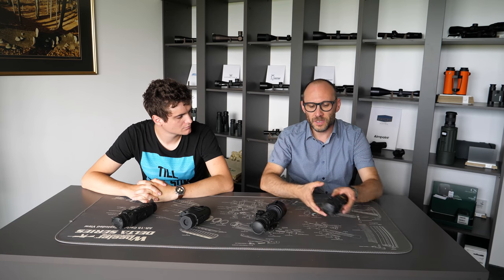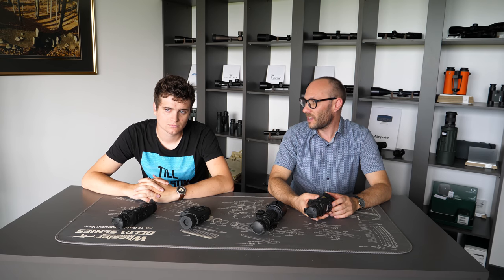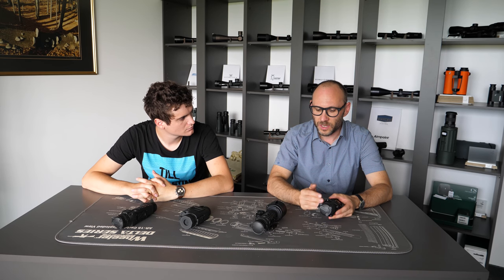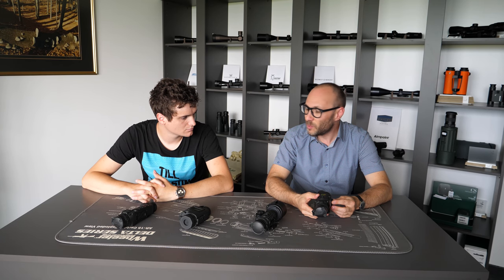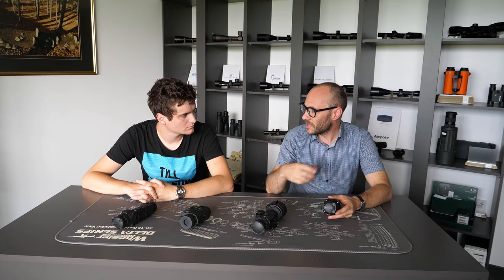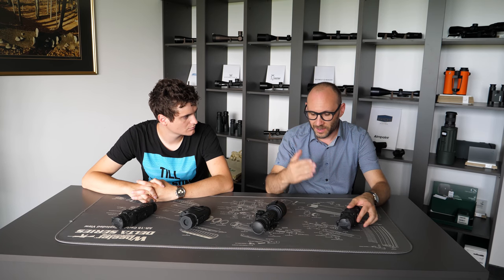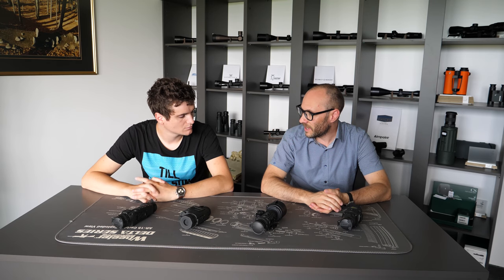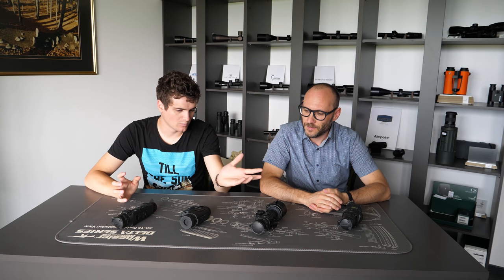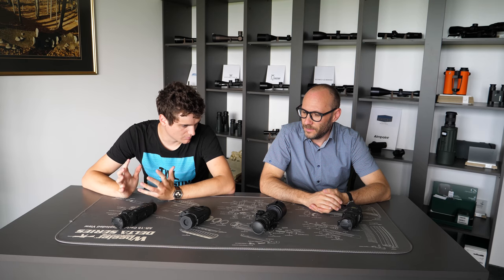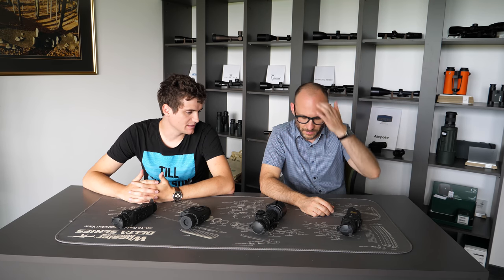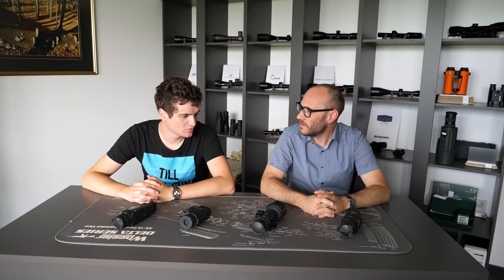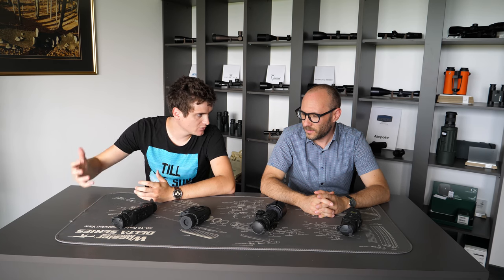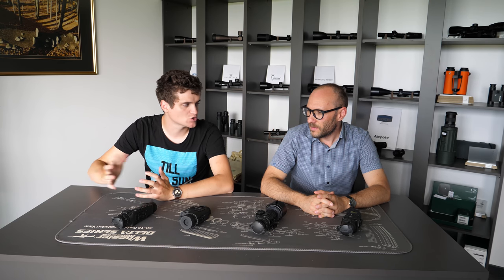When you power up the device, you hear the sound of the first calibration when the shutter closes. Then every minute or 2 minutes, this process is repeated. You see that the image freezes and you hear the shutter being closed and then opened again. So the manufacturer with these devices offers more than one calibration mode. And that's probably because every calibration mode is useful in a particular situation. So where would you recommend manual, automatic, semi-automatic? In which situations would you recommend them?